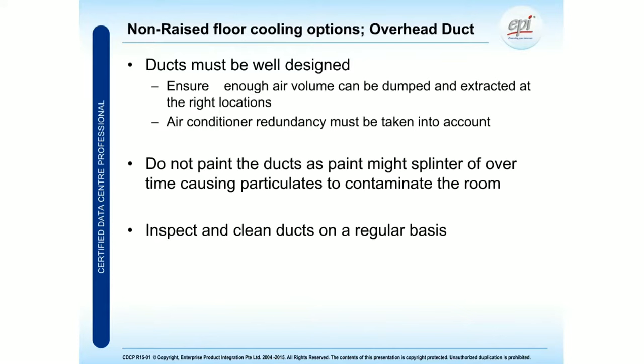If you don't have enough air, then it might cause hotspots as well. And also redundancy, because if we are going to apply anything such as an overhead duct system, and if the overhead duct is being serviced or maintained, or maybe it's not working anymore, then the redundancy must be taken into consideration, because this might have a huge impact on the available cooling capacity inside that particular aisle.